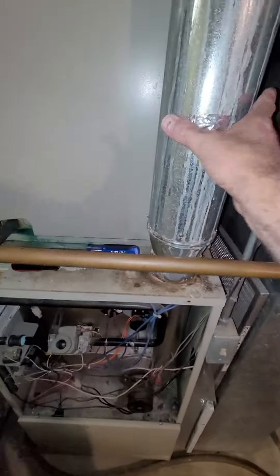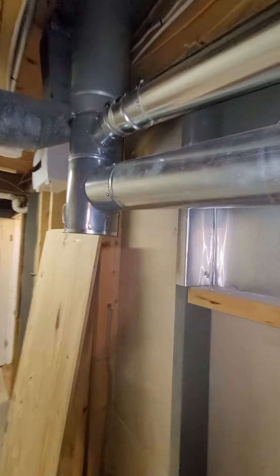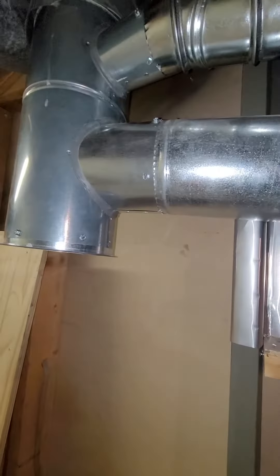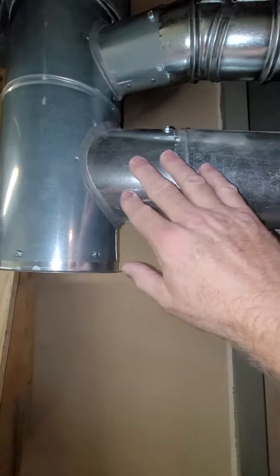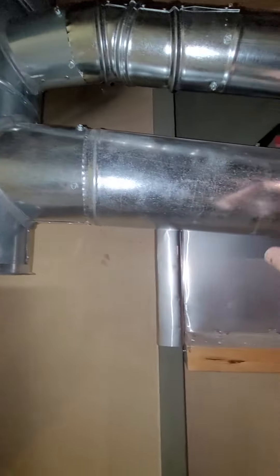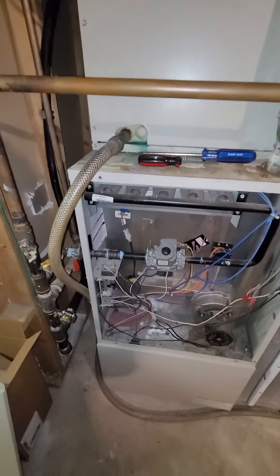As far as the flue, currently this one has a five-inch. It goes up to three, five, and six inch. This is all new, so really all we need to do is just reconnect right here. We'll hook onto that — it's a five-inch connection there. You may have to adapt up to it if you have a four-inch.